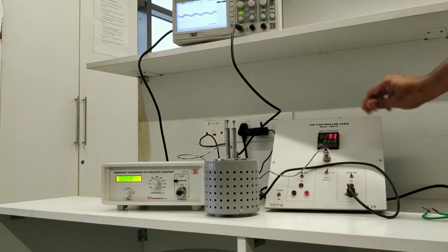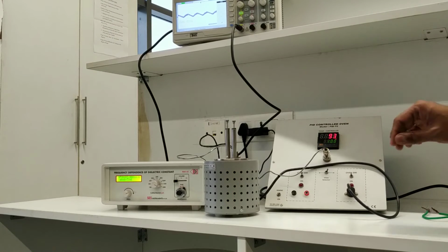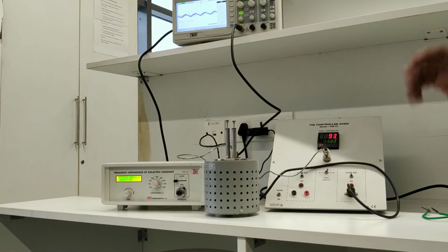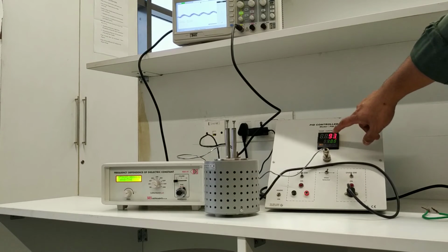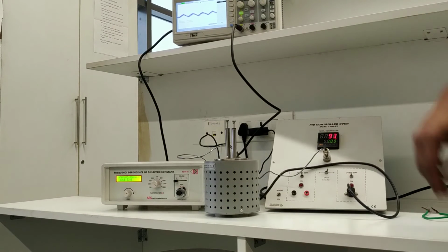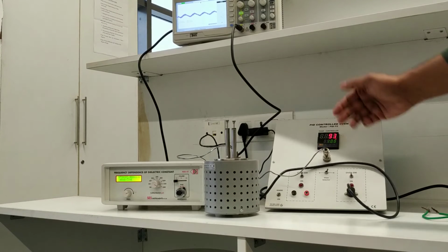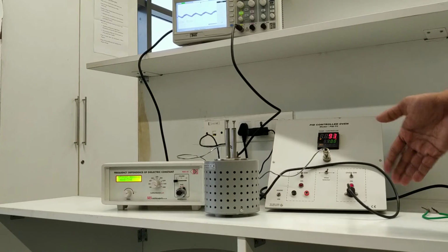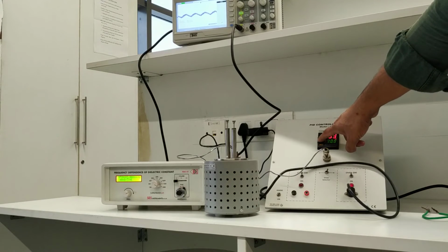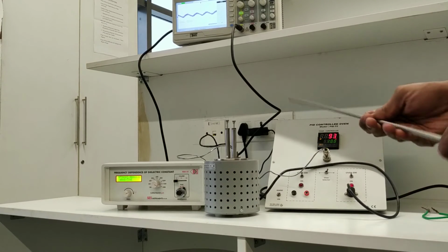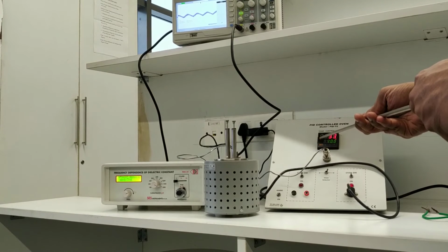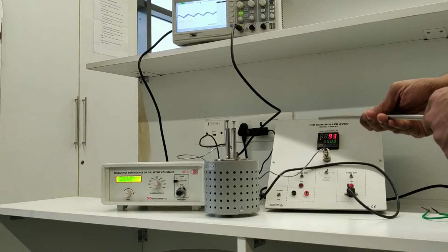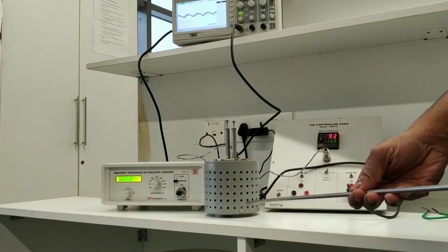Now you see the number is blinking. Within a few seconds it will stop blinking and it will automatically read this as the temperature I want to get. Okay, so now it will turn on. You will see in a moment it will turn on the heater and it will go to that temperature. Likewise you have to set different temperatures, allow the system to get to its equilibrium value at that particular temperature. You see now there is an orange LED that is on here, right? It says out 1. That means it is now outputting current to this oven, oven 1.